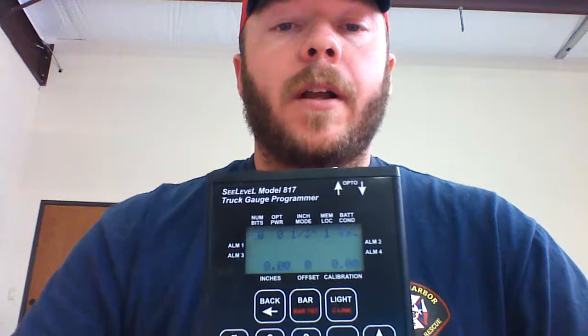And alarm 4 is most commonly used for our multi-rack system. The alarm 4 value will equal the alarm 1 value for your high-level shutdown. When a multi-rack is not being used, you can use the purple wire of the 808P2 as alarm 4, which will sound a backup alarm or light up a light, whatever you want to do with it.